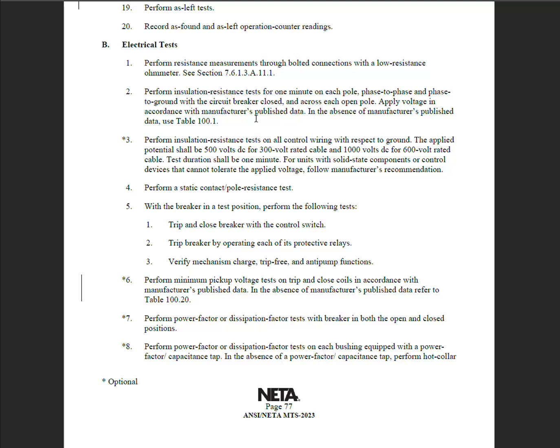Contact resistance, you might get lucky on some of these older ones to perform contact resistance. A lot of them either have pure mechanical pressure tests, or they're going to have millivolt drop checks on the older ones. Now, the newer vacuum circuit breakers and SF6s, a lot of these are going to have your contact resistance and your insulation resistance values and minimums and stuff like that. But a lot of these older breakers aren't going to. Okay, so we're going to go ahead. We're going to look at this. You can see that there was no real high pot listed here. If you look real close, dissipation factor, perform power factor, insulation resistance on the control wiring, yeah.